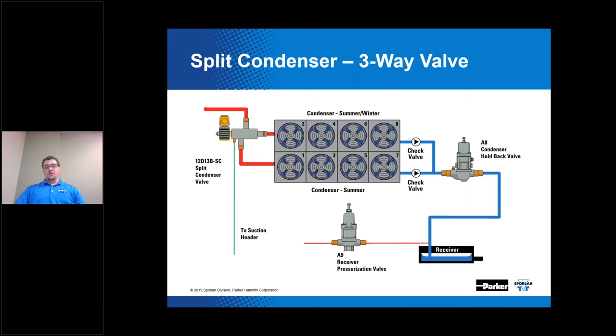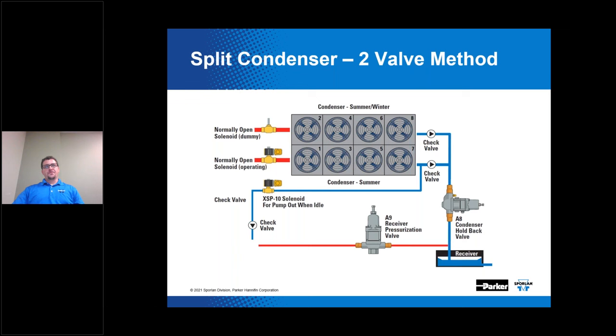In order to provide equal flow to both condenser circuits during full condenser mode or summer operation, you need another check valve at the summer/winter condenser outlet to introduce identical pressure drop through both halves. Without that check valve on the top half during high ambient when feeding refrigerant to both halves, you would not have identical pressure drop and would get more refrigerant flow to the summer-only condenser.